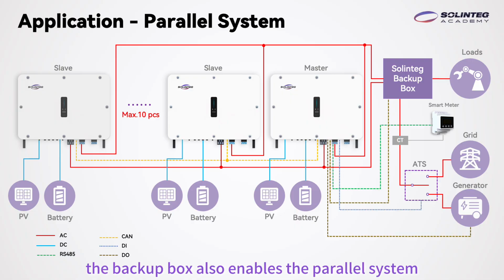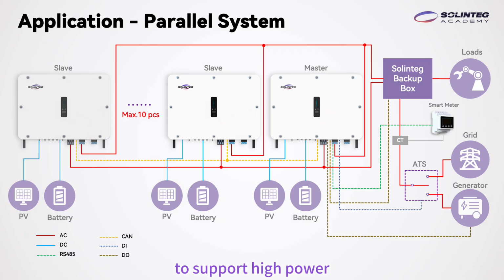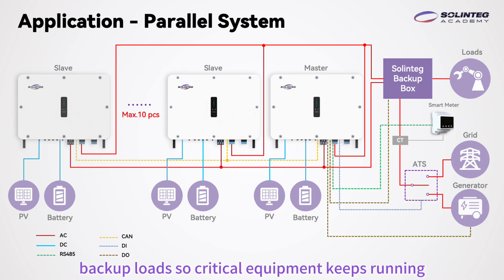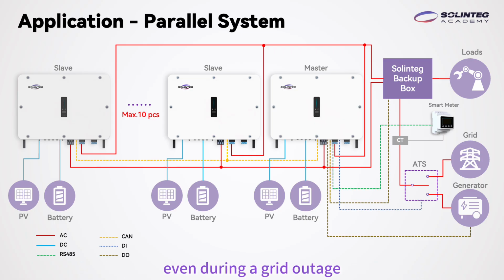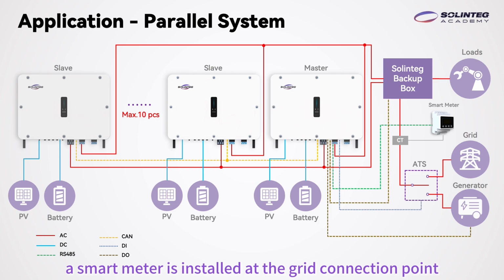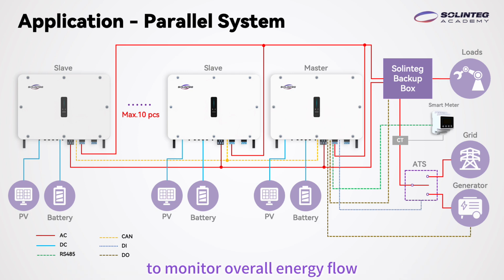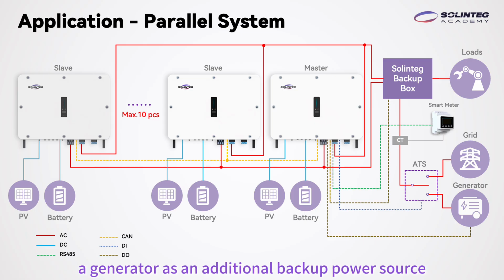The backup box also enables the parallel system to support high-power backup loads, so critical equipment keeps running even during a grid outage. A smart meter is installed at the grid connection point to monitor overall energy flow, and an ATS, or automatic transfer switch, can be added to integrate a generator as an additional backup power source when needed.